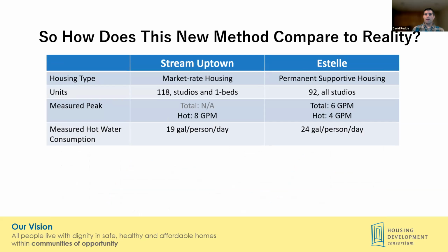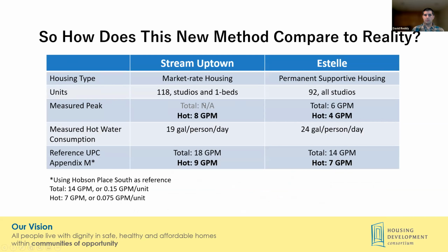So just to sum up what the difference is between the measured peaks. We have this hot water peak demand of 8 GPM for Stream, and using the Appendix M and assuming 50% of the water is hot, it's 9 GPM. So you can see it's very well aligned. And for Estelle, again, the Appendix M would have slightly overestimated the peak, but it gets to that load profile. The load profile for permanent supported housing does not have that very high peak morning, and that's reflected in the data. So the Appendix M would be more conservative for that application.